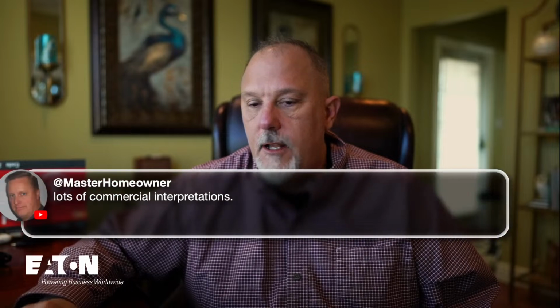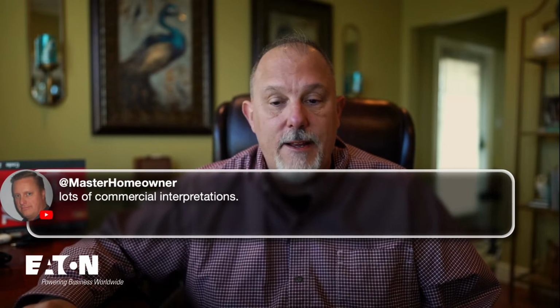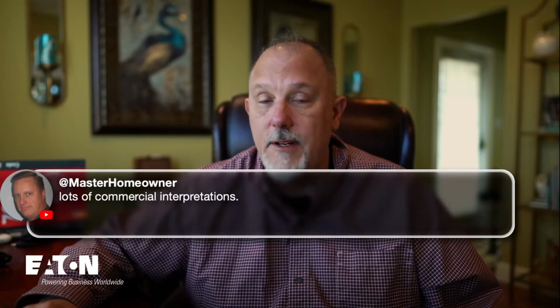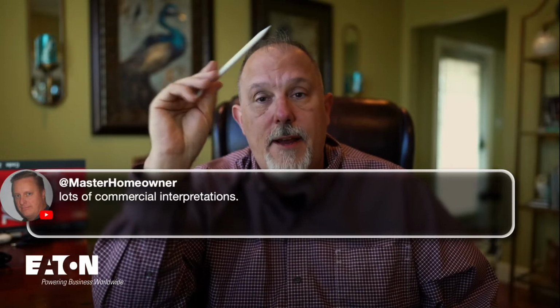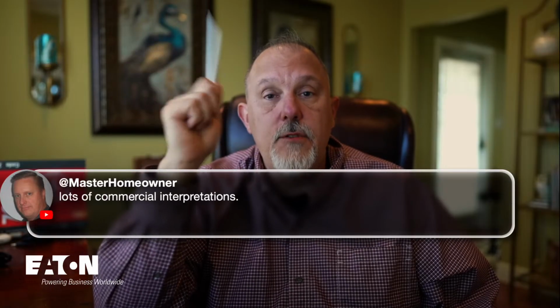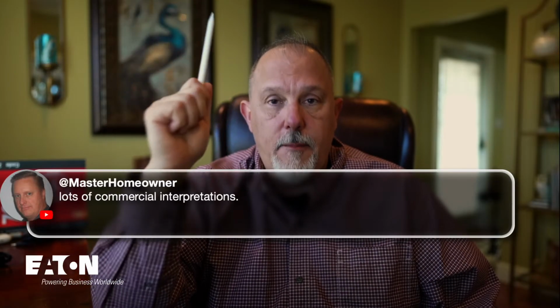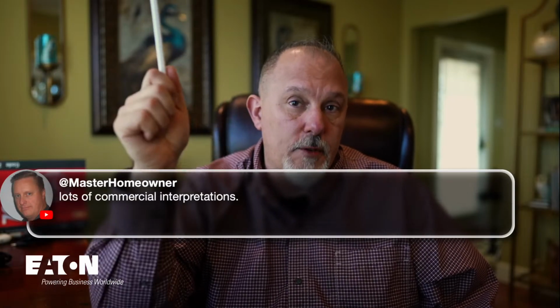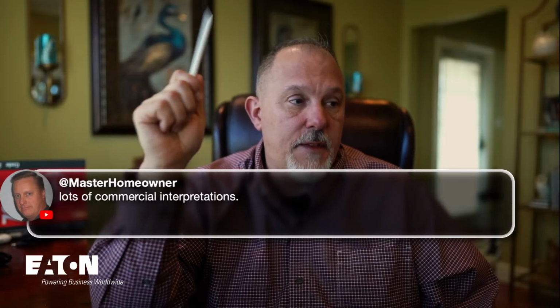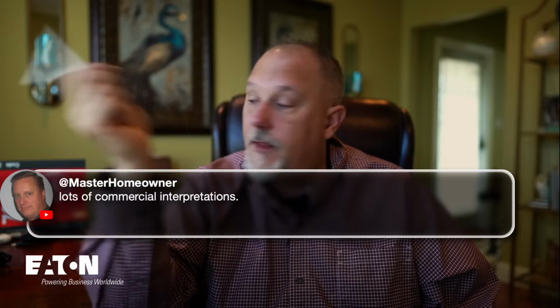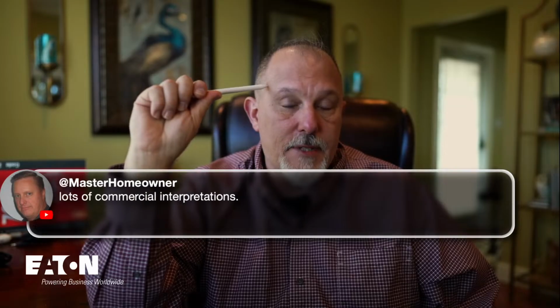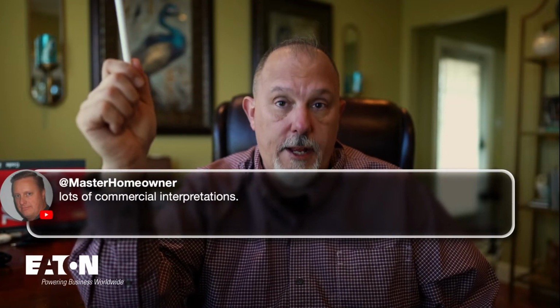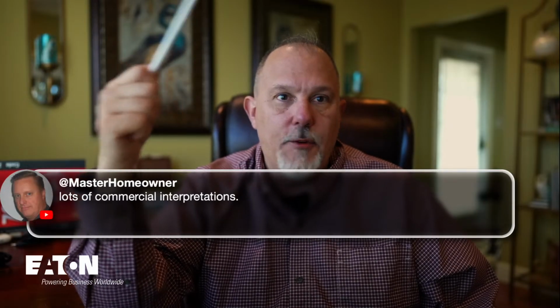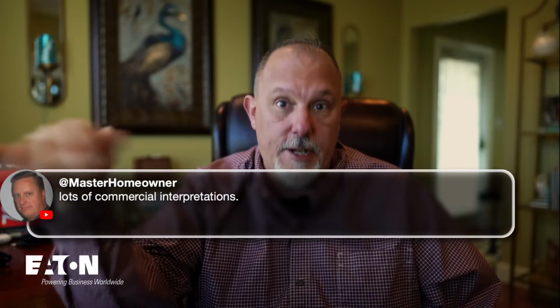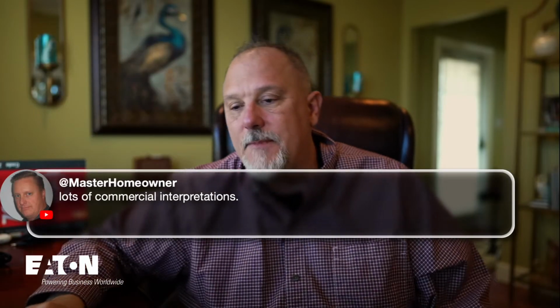Anyway, lots of commercial interpretations, I don't know. I'd love to know which one's a commercial interpretation, because everything I've said so far is all factual. The only thing that's different is whether or not a manufacturer publishes the right data. So I do question some manufacturers' data, because I don't know if it was written by a commercial person or an engineering person. I've seen ratio tables that say these two breakers will selectively coordinate up to 10,000 amps, and it ain't going to happen. They mean coordinate at 0.1 seconds, and you can't throw amps in there, because the moment you throw amps in, now you're into the selective coordination discussion, or a coordination discussion that's not a 0.1 seconds thing. So that's my only thing there.